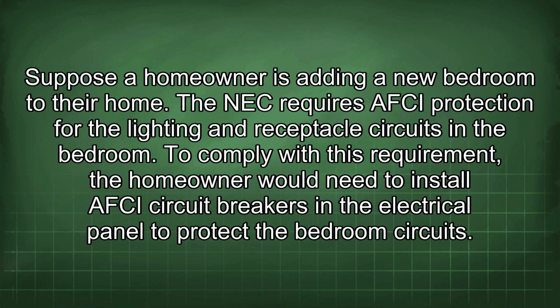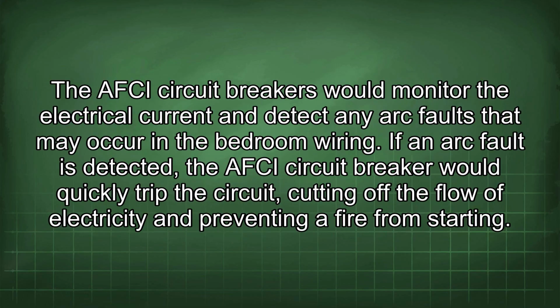Suppose a homeowner is adding a new bedroom to their home. The NEC requires AFCI protection for the lighting and receptacle circuits in the bedroom. To comply with this requirement, the homeowner would need to install AFCI circuit breakers in the electrical panel to protect the bedroom circuits. The AFCI circuit breakers would monitor the electrical current and detect any arc faults that may occur in the bedroom wiring.